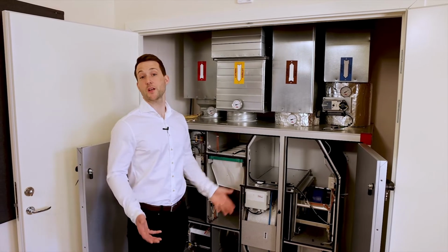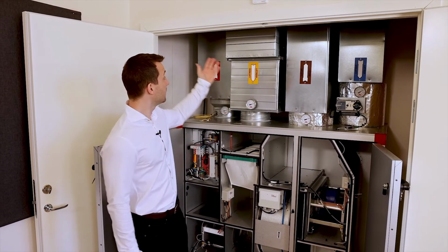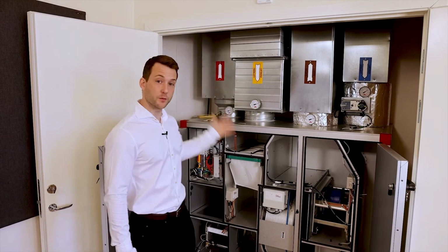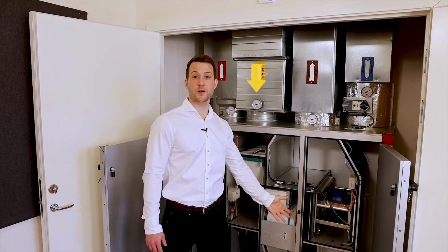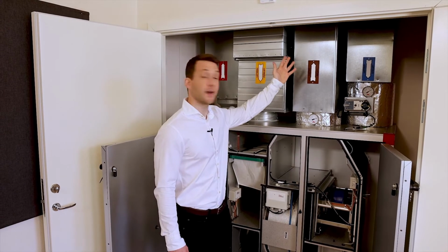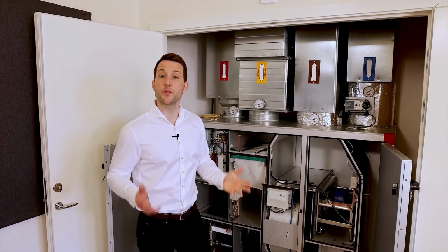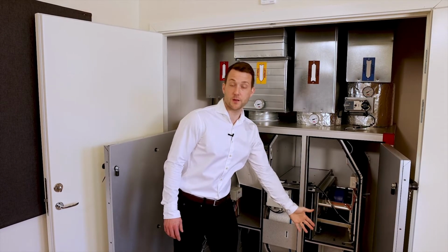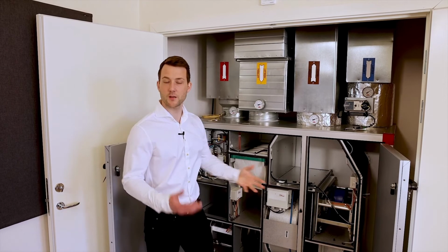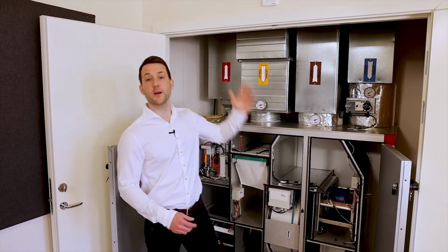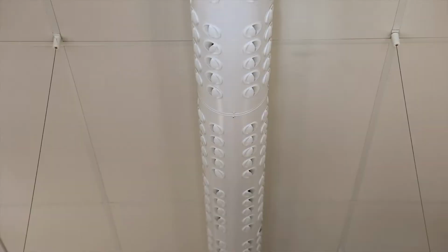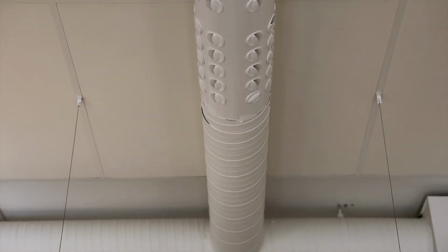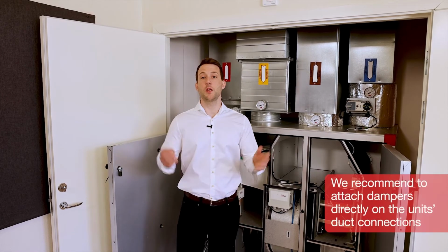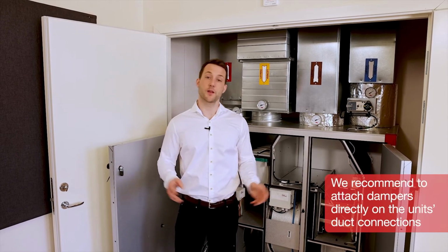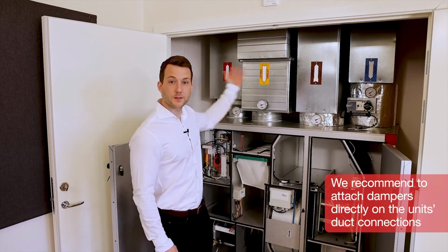So, the earlier mentioned extract air that goes through the ventilation grill comes into the unit here, goes through a filter, through the rotary heat exchanger, and then leaves the unit over here as exhaust air. The fresh outside air you will find over here goes into the unit, through a filter, passes the rotary heat exchanger, takes the energy, and is then being supplied evenly throughout the whole classroom via those adjustable diffusers we saw earlier. To keep the noise level as low as possible, they installed dampers on all ducts.